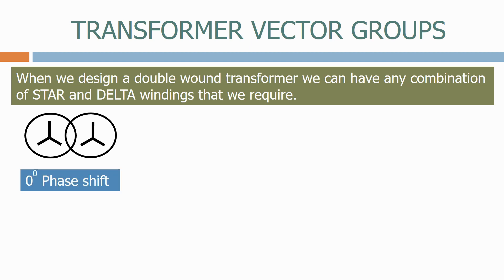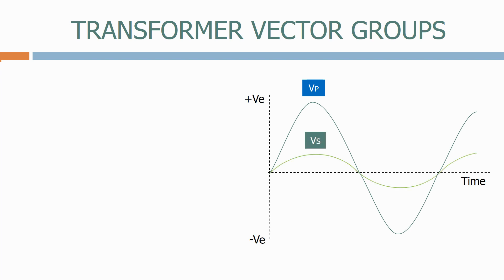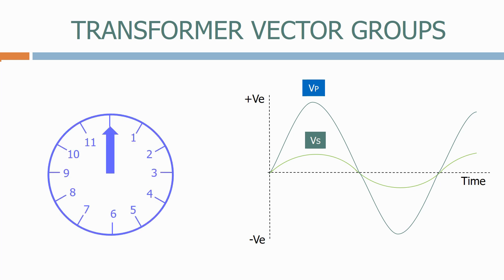A zero-degrees phase shift means that the voltages on the primary and secondary windings are both in phase, and there's been no phase shift from the primary to the secondary winding. A simple way to show the phase shift across the transformer is a clock face, with zero degrees at the top. We then show the phase shift in 30-degree increments.